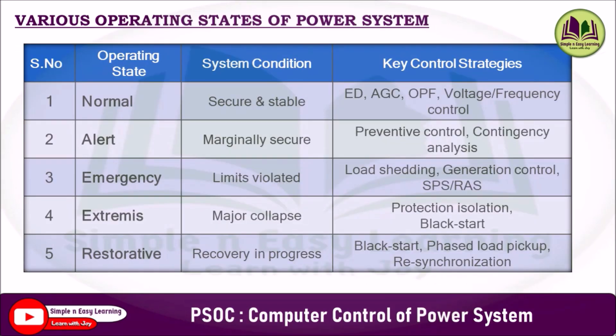In summary, there are five operating states of a power system: Normal — system is secure and stable; key strategies are economic dispatch, automatic generation control, optimal power flow, and voltage/frequency control. Alert — system is marginally secure; key strategies are preventive control and contingency analysis. Emergency — operating limits are violated; key strategies are load shedding, generation control, and special protection schemes. Extremis — major collapse occurred; strategies involve protection isolation and black start. Restorative — recovery in progress; strategies include black start, phased load pickup, and resynchronization.